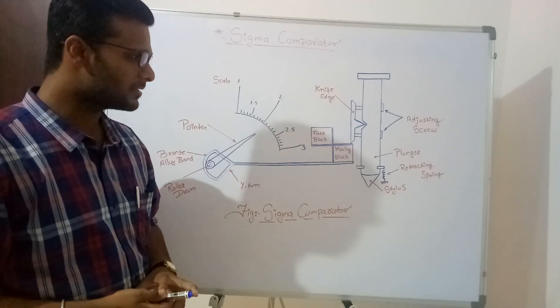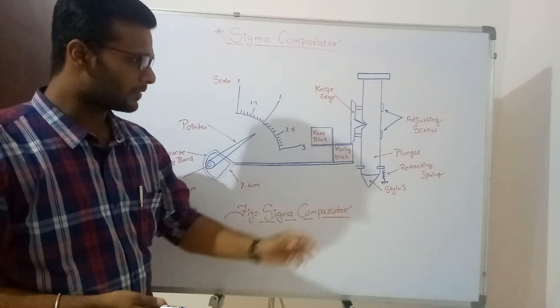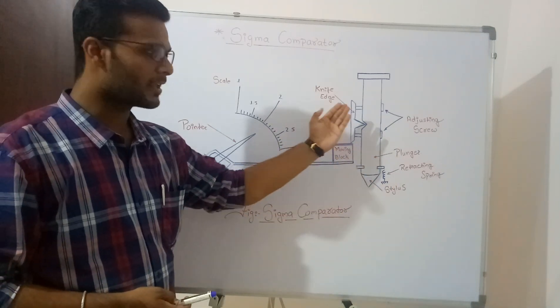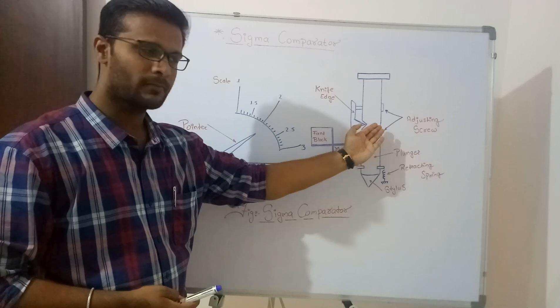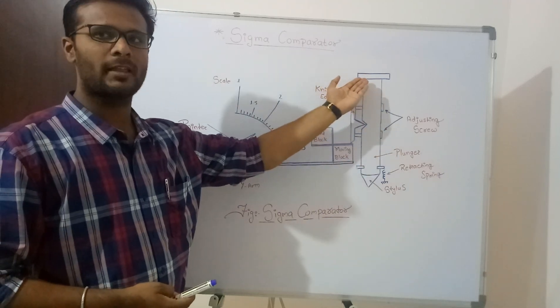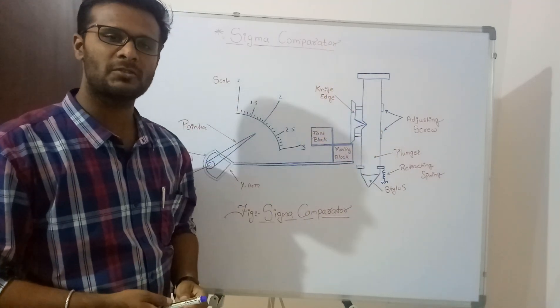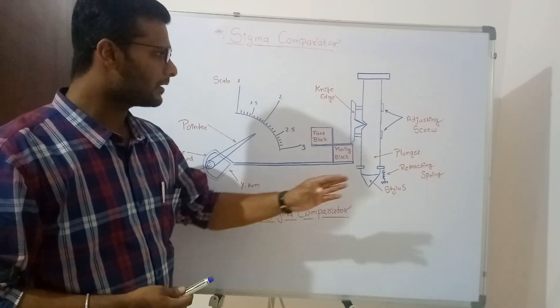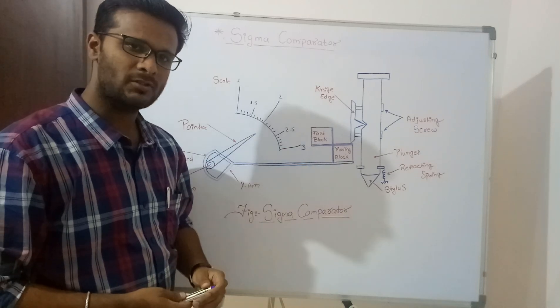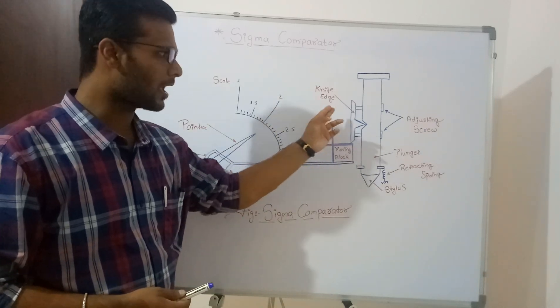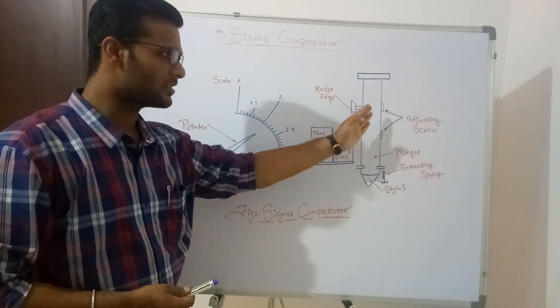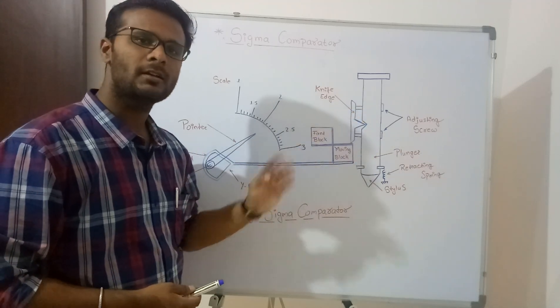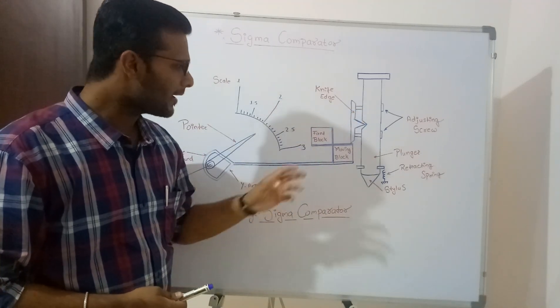First of all we will see construction of Sigma Comparator. It comprises of a plunger, a stylus, retracting spring. After retracting spring it has arrangement for adjusting screws. Above there is a diaphragm. In some cases the diaphragm is not provided directly, a spring is provided, and adjusting screw is there. After that we are having over here a knife edge through that knife edge we are having adjusting screws which can be adjusted.